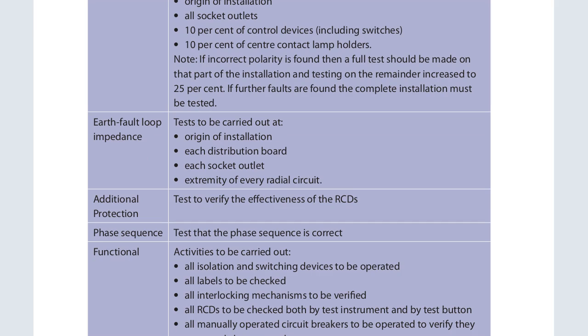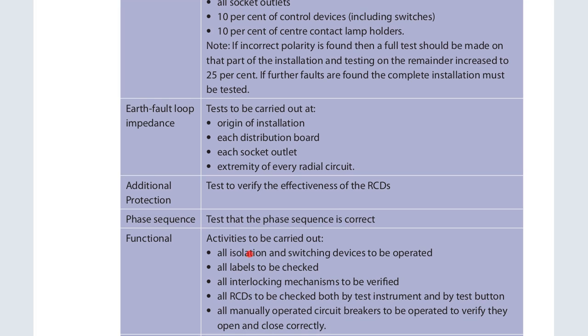The earth fault loop impedance. This is a test carried out at the origin of the installation, also at each distribution board, at each socket outlet, and the extremity of every radial circuit. And then we have additional protection, that is the test of the RCDs. We also have the phase sequence test, that is the test that the phase sequence is correct. We have the functional test, that is activities to be carried out on all the installation. We make sure that the isolation and the switching devices are operated.